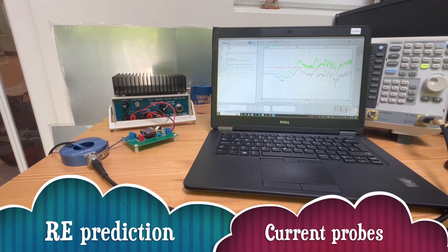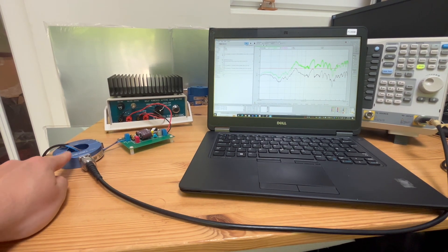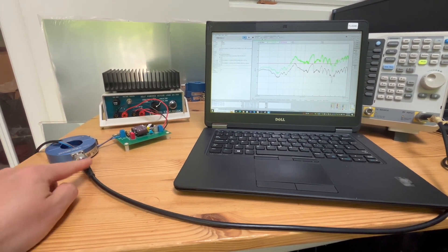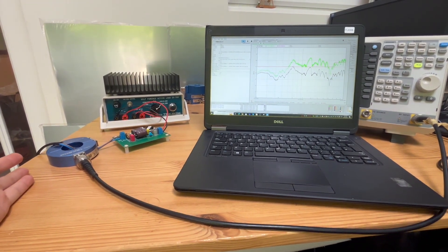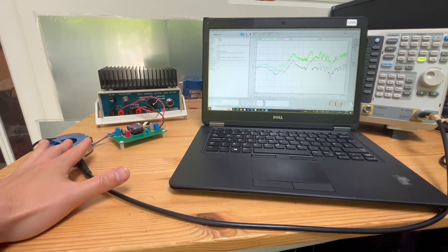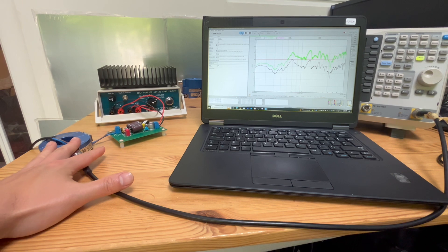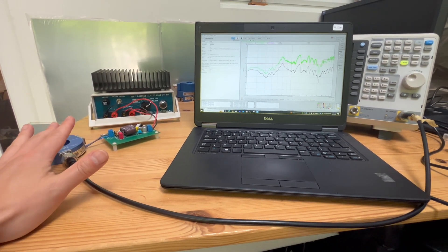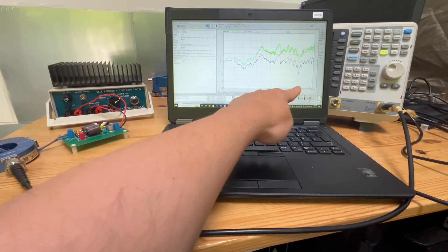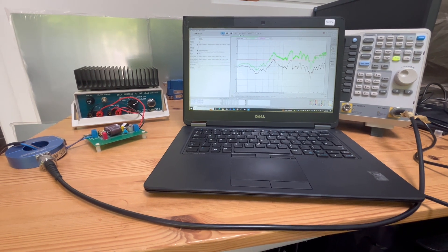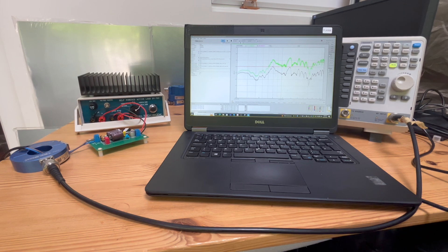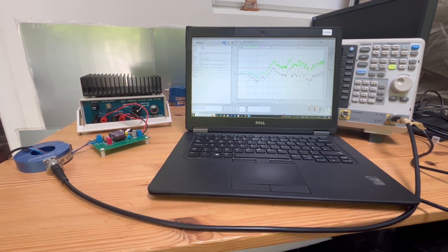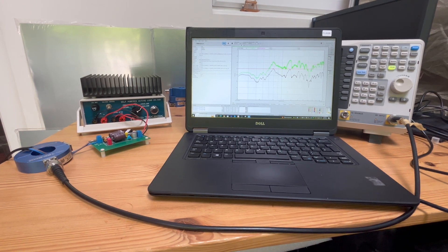Another very useful application of an RF current probe is you measure the common mode current on the cable, and then you can predict the far field's radiated emission results. This method is particularly useful if you are dealing with power electronics applications, and it's also useful in terms of the frequency range between 30 megahertz to about 300 megahertz. If you want to know more about this subject, we have another video which is called Engineer's Guide to Radiated Emission Test, which is very popular on YouTube. I have put the link in this video as well.